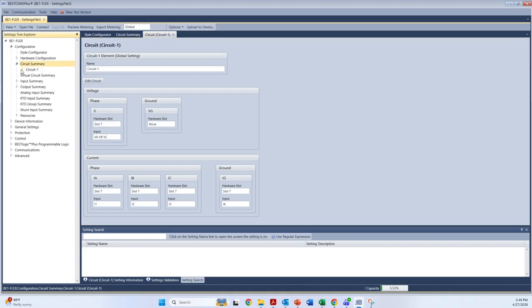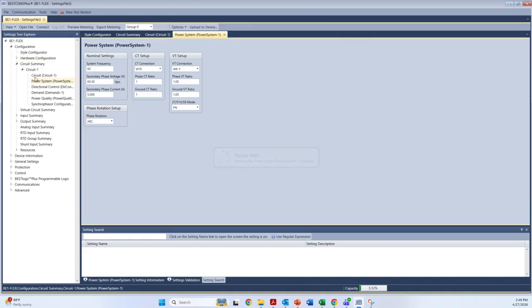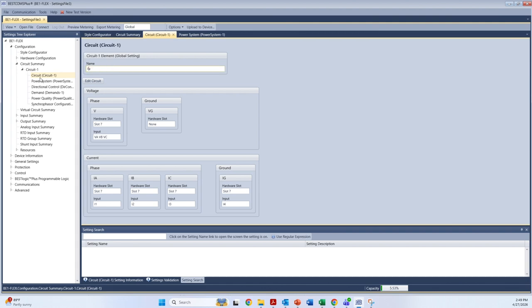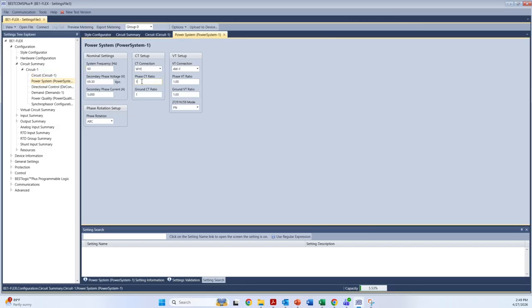You also have to put in some power system parameters. You can also give it a name if you want. So for instance, if it's 2000 to 5 CT inputs for the 3-phase CTs, you would put in a value of 400. And if it's a 480 to 120 PT input, you put in a ratio of 4.